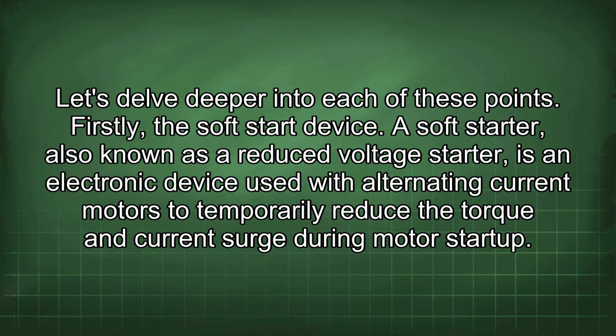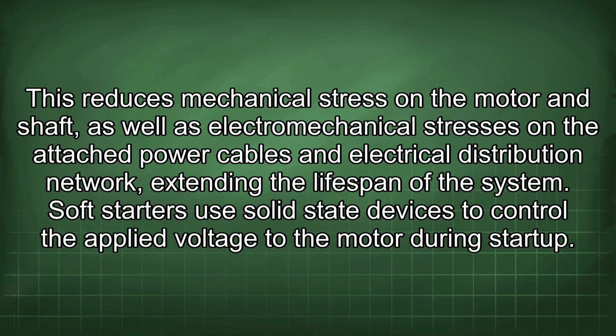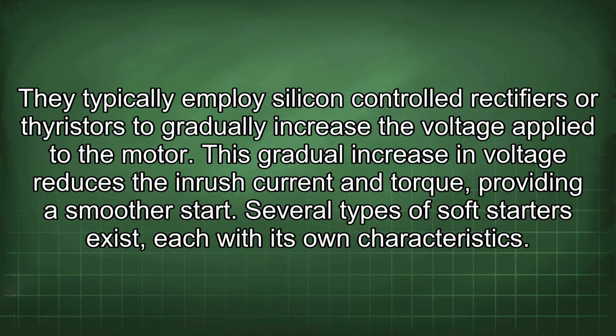A soft starter, also known as a reduced voltage starter, is an electronic device used with alternating current motors to temporarily reduce the torque and current surge during motor startup. This reduces mechanical stress on the motor and shaft, as well as electromechanical stresses on the attached power cables and electrical distribution network, extending the lifespan of the system. Soft starters use solid-state devices to control the applied voltage to the motor during startup. They typically employ silicon-controlled rectifiers or thyristors to gradually increase the voltage applied to the motor. This gradual increase in voltage reduces the inrush current and torque, providing a smoother start.